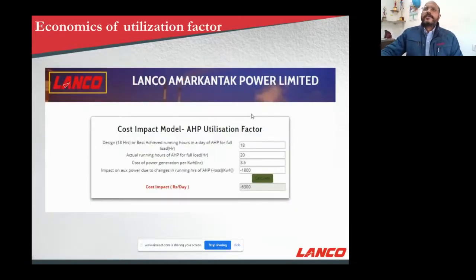For example, we are talking ash handling plant utilization factor. This is purely based on the amount of running hours the ash handling plant is taking rest or continuously running, and then the amount of the auxiliary power consumption out of that with respect to the best achieved. And then cost impact is assessed. So we can always sensitize the local engineer, see, if effectively handled, we can take up to design, like 6 hour operating, 2 hour rest. If this is the regime, then we are okay, or otherwise if we are exceeding, we are coming to loss of this amount. Basic concept is converting all these parameters into financial terms and establishing a relationship on that.